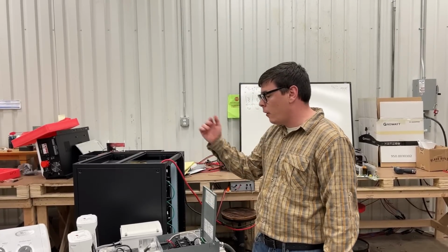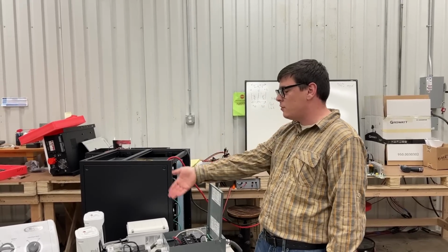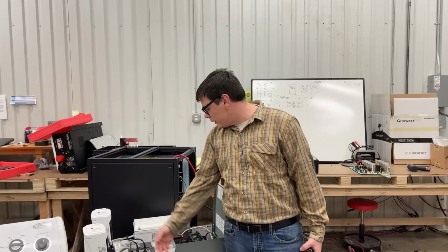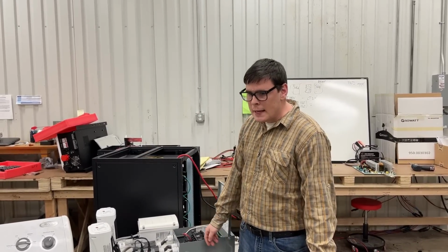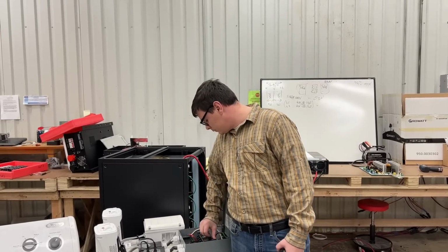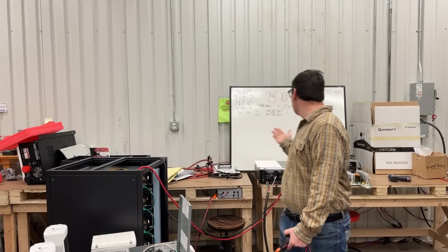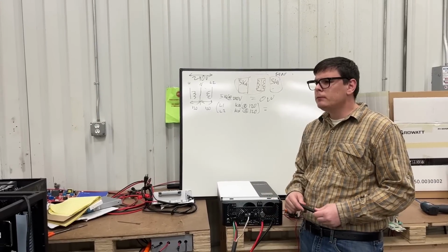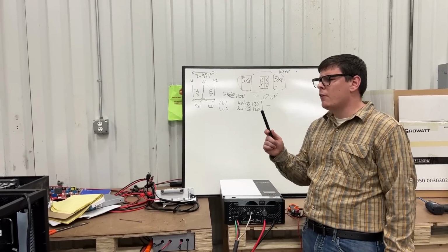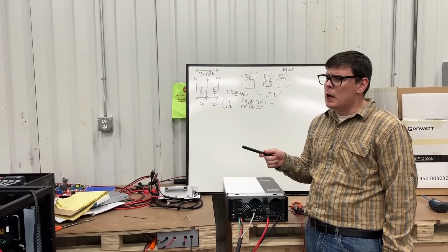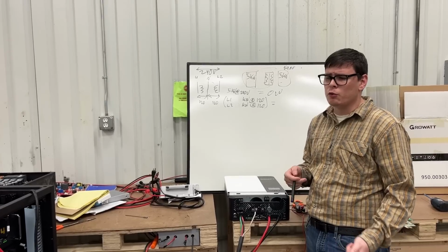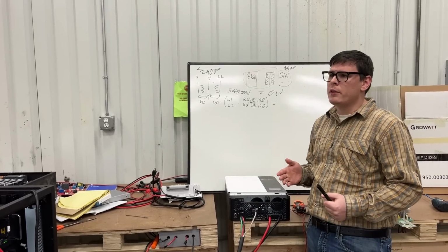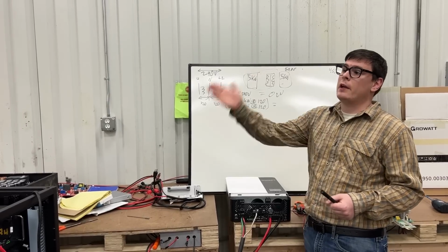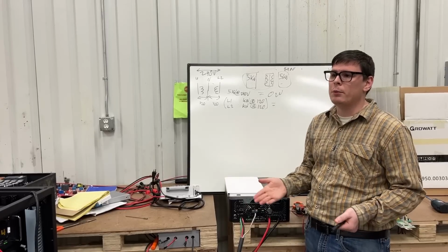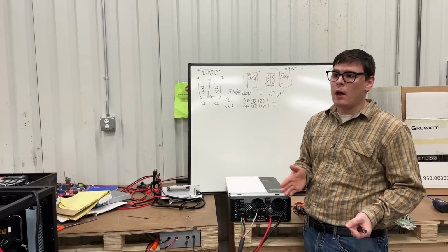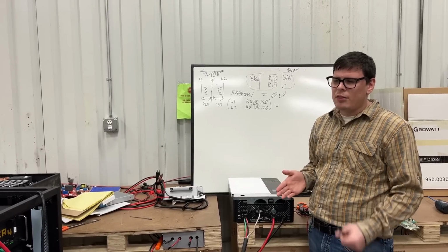So at the end of the day, yes, if I wanted to make a scene, I could go grab 10 of these heaters and plug them all on line 1 and run this transformer up to 240 volts, but that's just not practical. So hopefully that just illustrates the key points that we have here. So we're going to show you guys what we have, a larger main distribution panel. We'll take this video to show you what happens when something goes wrong, because I think everybody's tripping this out, assuming that they took that lineup of 10 heaters and then turned it off, and yes, you have full potential. But if you were semi-balanced before and grounded, then you're not going to hit things with 240 volts.